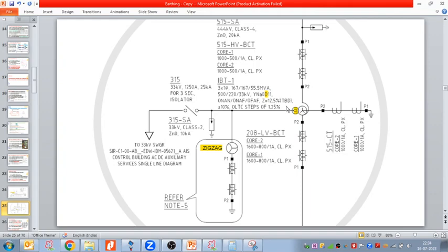That winding is connected in delta, and this is going to feed the LVAC system of the entire electrical installation. As you can see, it is going to feed the 33 kV switchgear. So to achieve the grounding on this part of the circuit, we are going to use this zigzag transformer, and this is a single winding as I told.